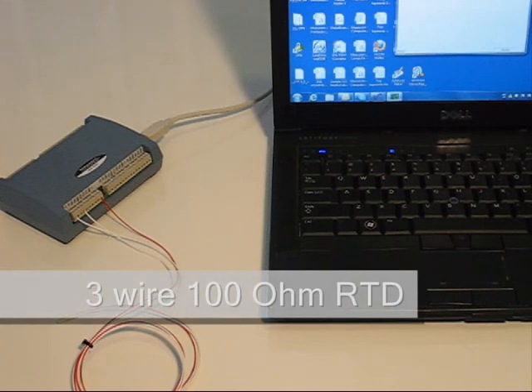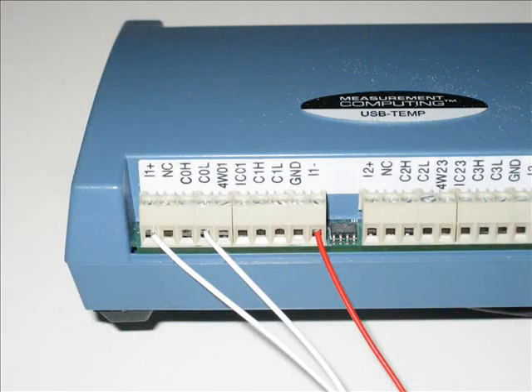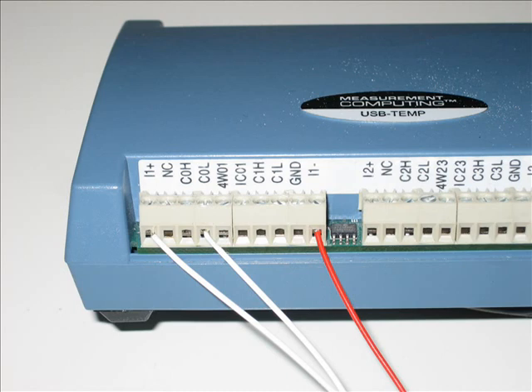The three-wire RTD connects to channel 0 low and the channel 1 plus and minus current excitation terminals. The USB temp supports two, three, and four-wire RTDs.